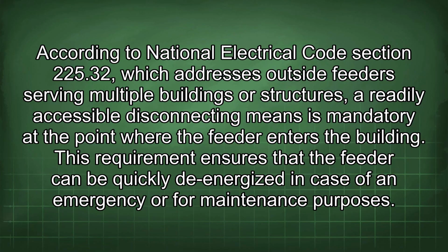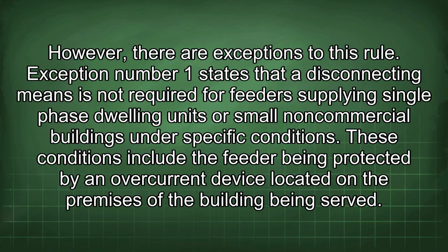According to National Electrical Code Section 225.32, which addresses outside feeders serving multiple buildings or structures, a readily accessible disconnecting means is mandatory at the point where the feeder enters the building. This requirement ensures that the feeder can be quickly de-energized in case of an emergency or for maintenance purposes. However, there are exceptions to this rule.